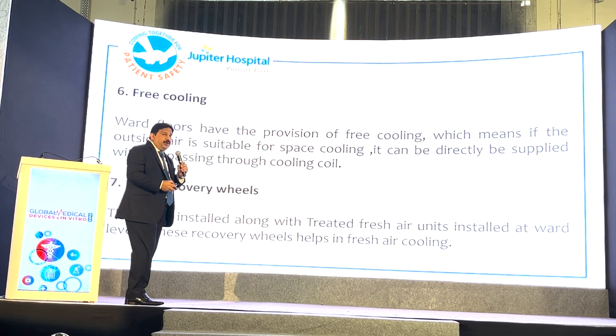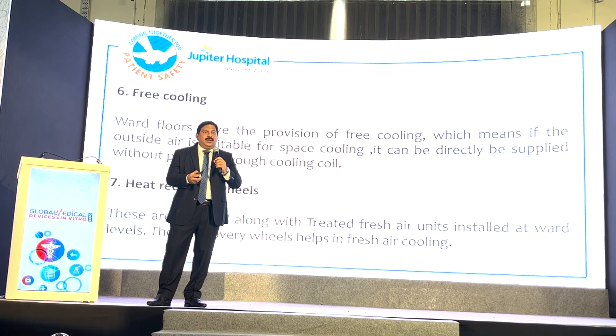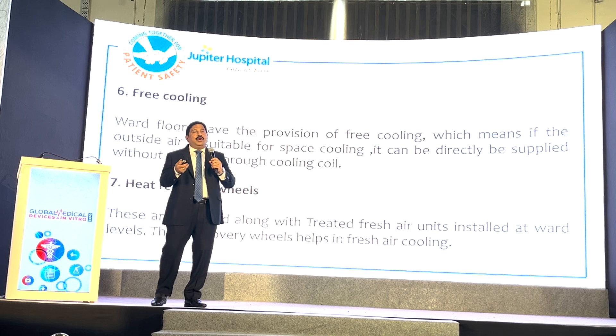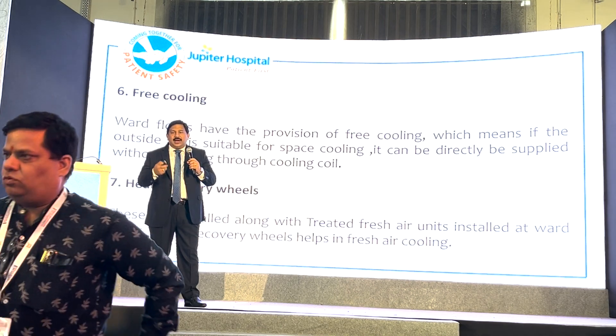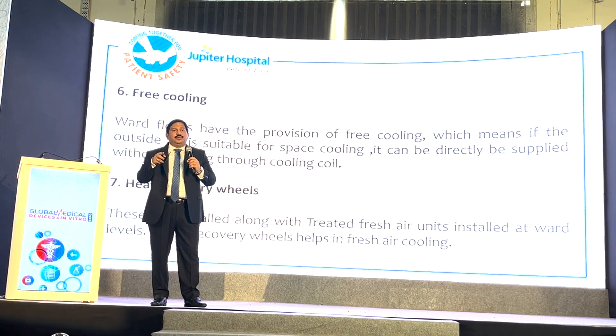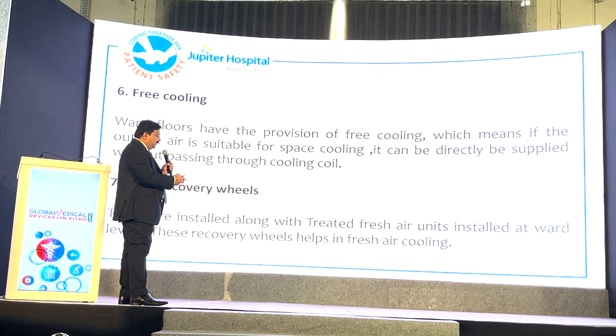Now, free cooling — why is there a free cooling advantage? In a city like Pune, in winter season the temperature goes down to 9 to 10 degrees. If you have 9 to 10 degree temperature available, why not use it? We are giving chilled water supply at 7 degrees and reducing the temperature below that from outside. Instead, if 8 to 9 degrees is available, we should use it with free cooling, and then heat recovery wheels. These are the things we can use for energy saving.